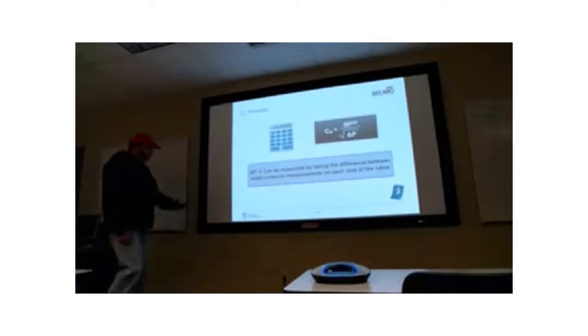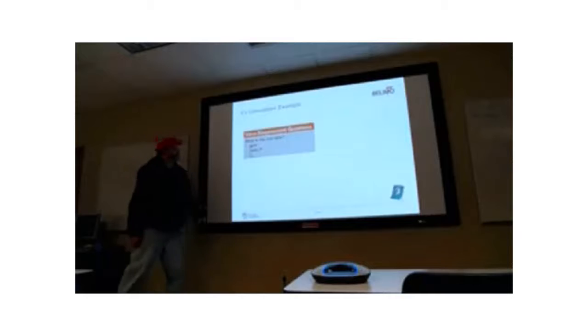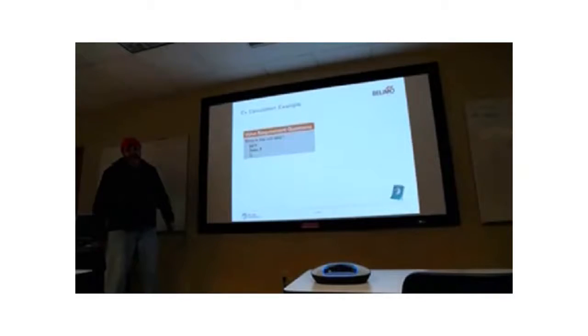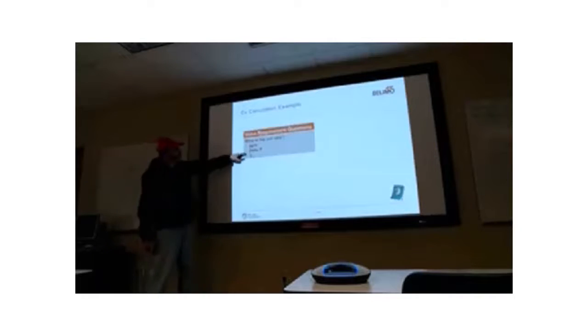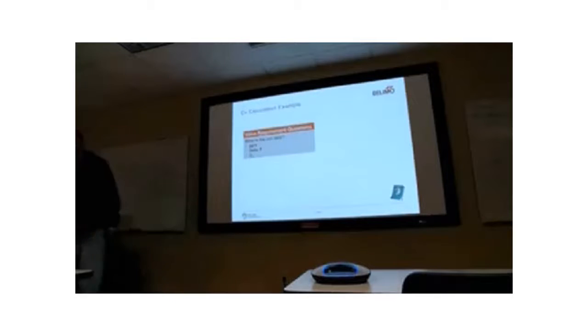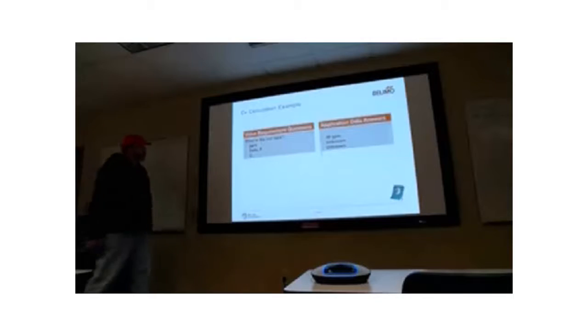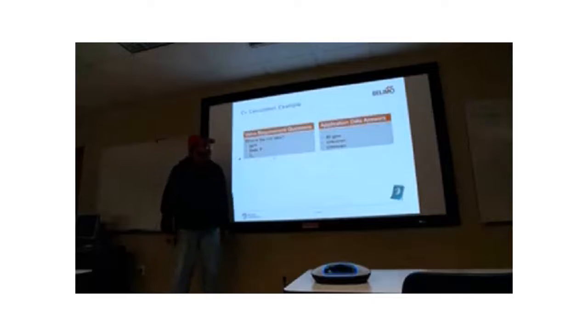P1 minus P2. Now, we're just going to do an example to show you how this works. We're not going to get all wrapped up in the math, but I want to show you how it works. The first thing you've got to know is these two things right here. You need to know the design flow rate, whatever that coil is supposed to be doing at maximum flow. And then you've got to figure out what this pressure drop is if somebody doesn't already give it to you. So in this case, we're going to say we've got a 40 GPM coil.